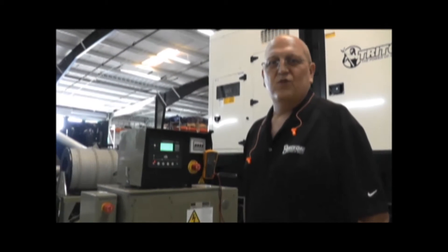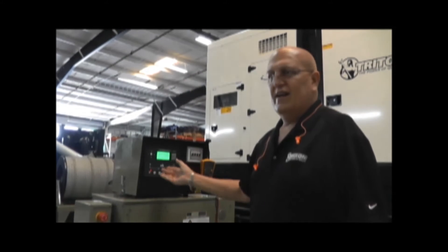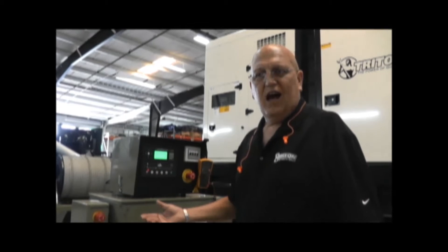At which time you would need to try to reset the fault, clear it, and start the generator again. If the fault persists, I'm going to show you steps you would take to diagnose that the AVR is bad, at which time you would get a new one and replace it.